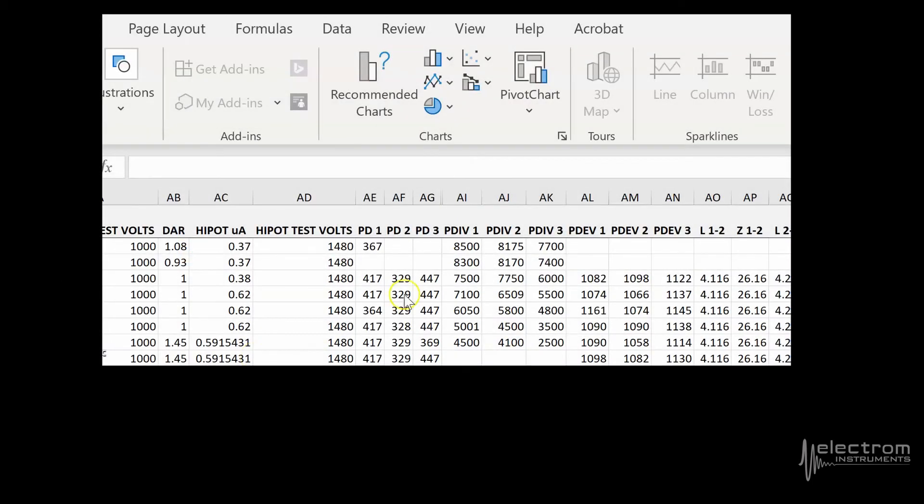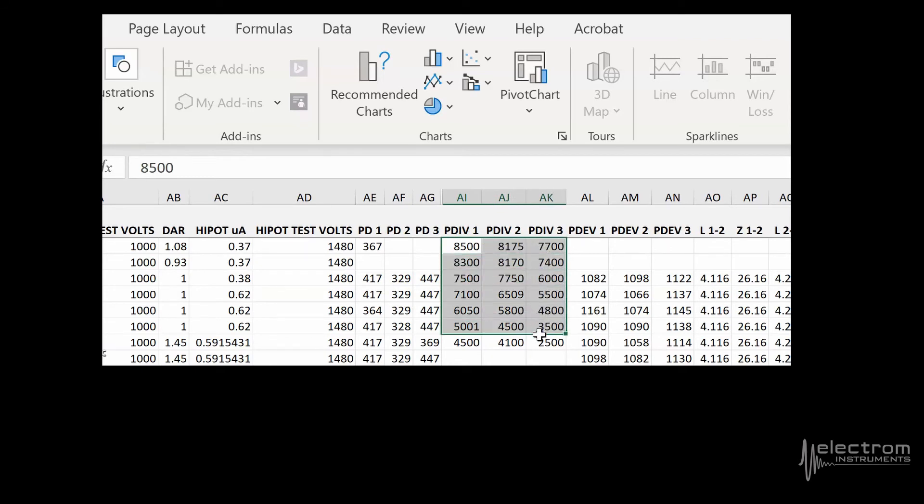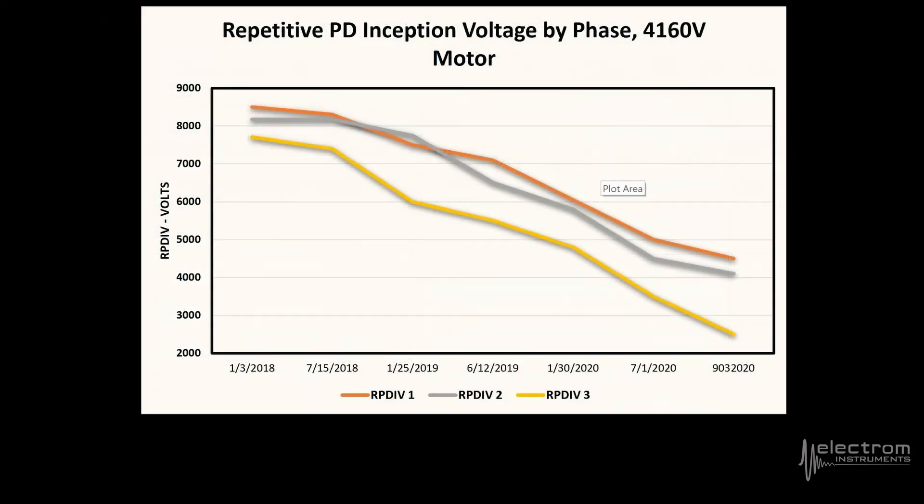Trending is easy with the test summaries file available with the D model. Select the desired test data collected over a time range, then chart it. In this case, we see repetitive partial discharge inception voltage, or RPDIV, is trending downward.